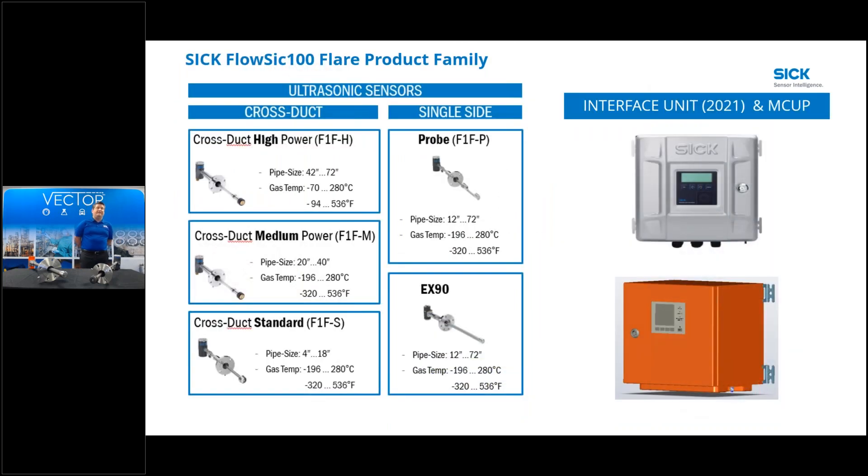The SICK FlowSic100 Flare family has two versions of sensors: a cross-duct type and a single-sided type. On the cross-duct side we have three versions based primarily on pipe size - thumb rules are 4 to 18 inch, 20 to 40 inch, and 42 to 72 inch. Every flare will be evaluated for the right fit based on gas composition and installation capability. You may have a high-power requirement in a 24-inch line, for example.